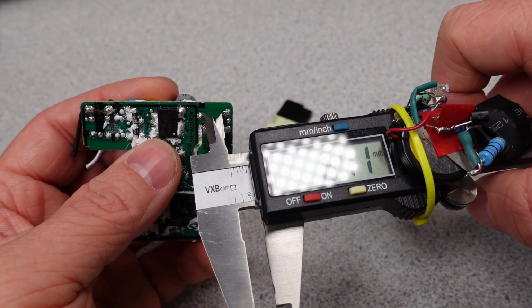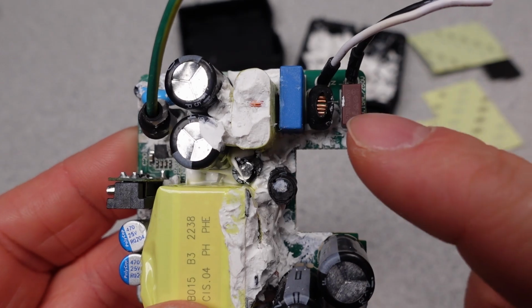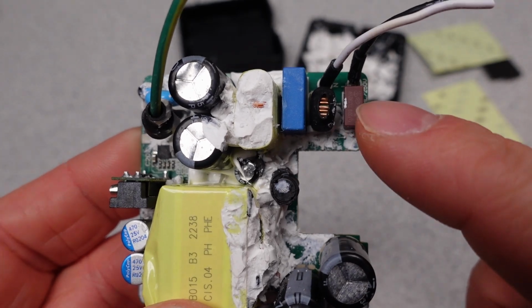This device has a fuse on the input AC connection. The fuse is rated 3.15 amps. This is a standard feature and non-resettable, so once this pops, the adapter will not function. This is a high enough value though that if this fuse pops, then the major failure has occurred.